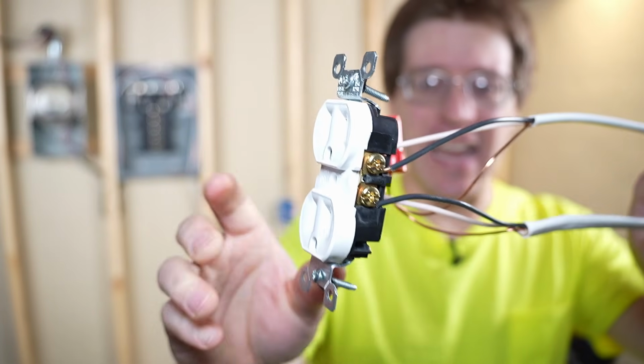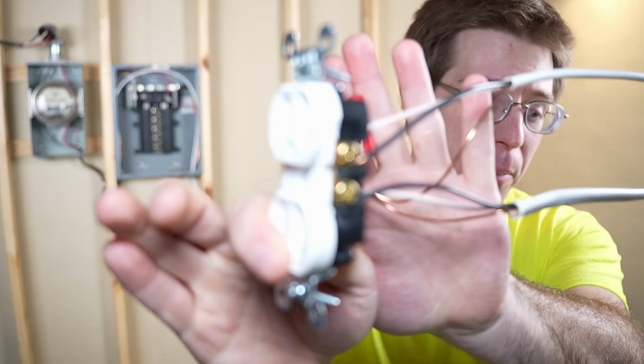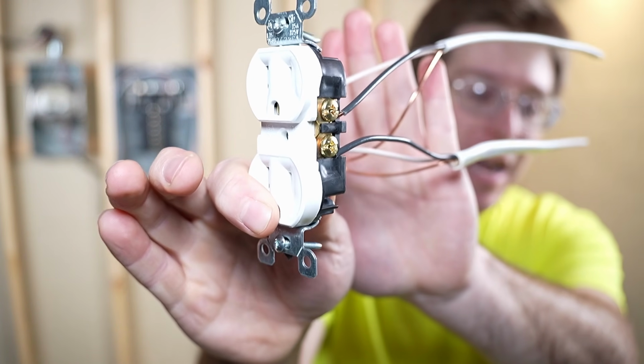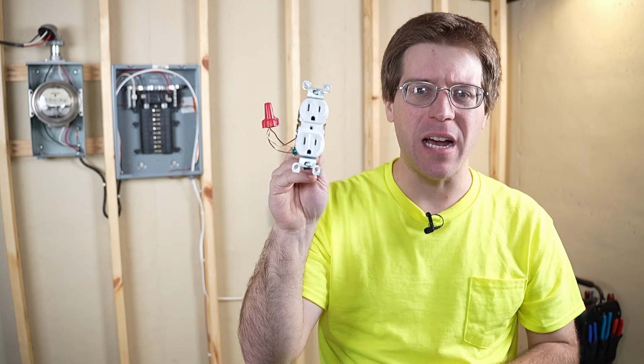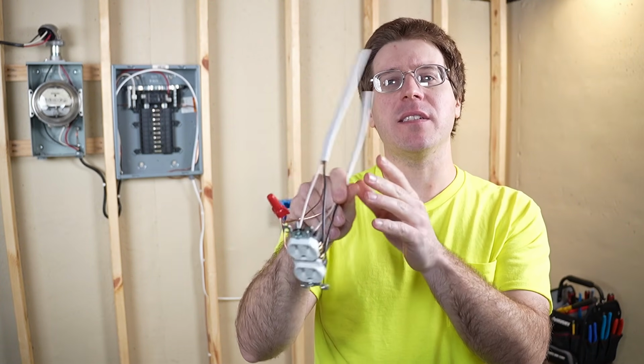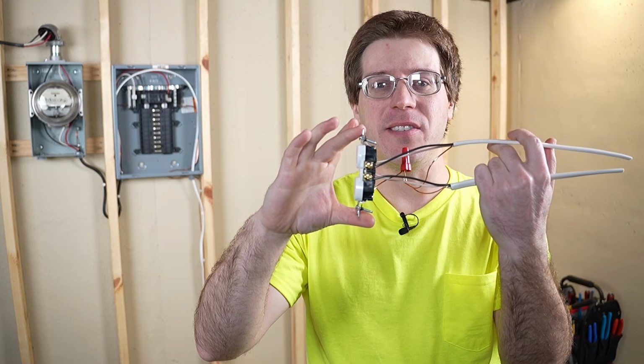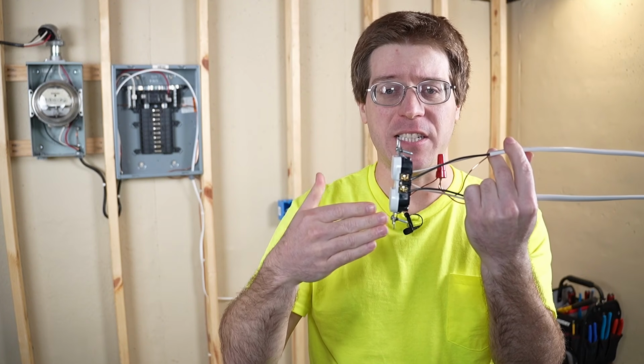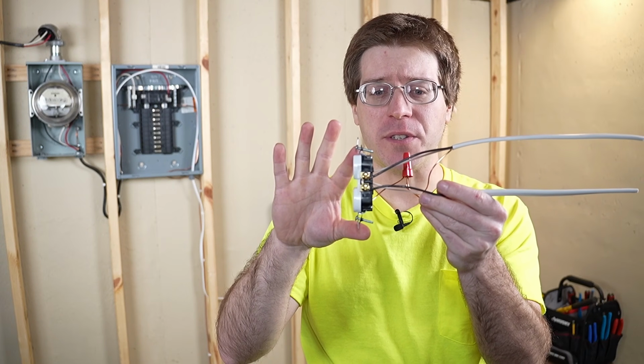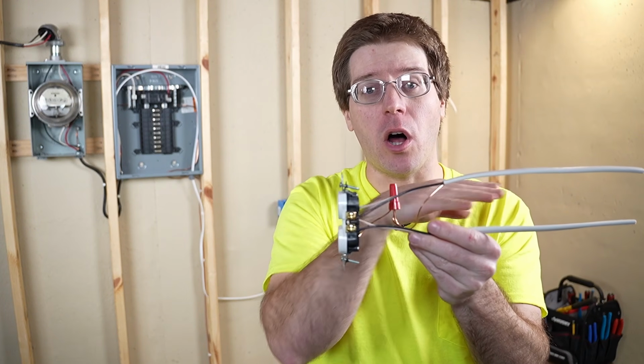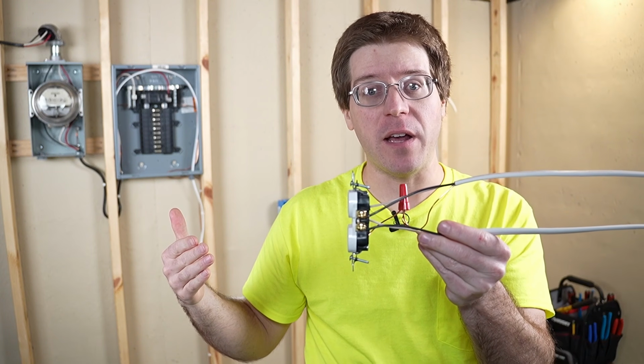But this is another method. A lot of people, myself included, do not like this method. Most, not all, but most electricians do not like this method simply because we are relying on the receptacle itself as a splice. So if this receptacle were to fail, it might cause all the downstream receptacles to fail also.